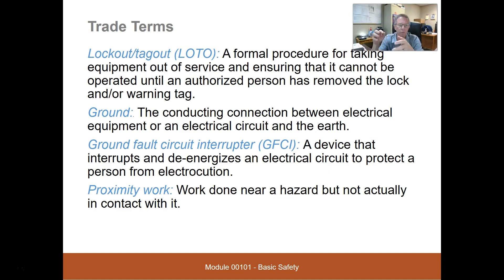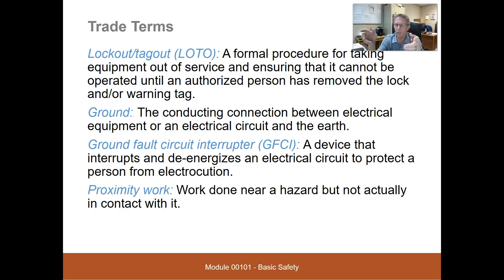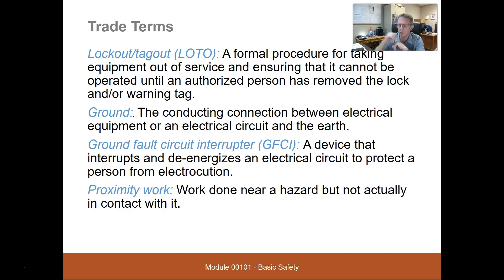On the job site, a lot of the shocks we receive come from moving a wire or tool that's plugged in where one wire is skinned out. A GFCI would see that imbalance when it's really small — before it gets big enough to hurt us — and turn it off in 1/40th of a second. Circuit breakers and fuses are wire and equipment protection.